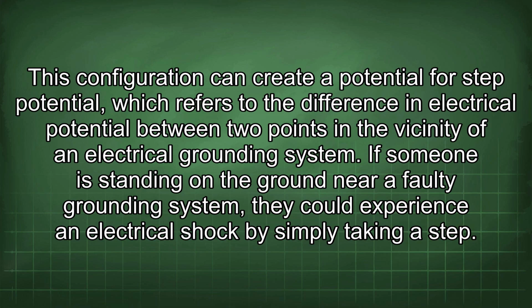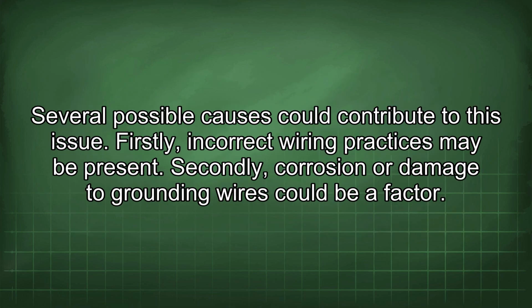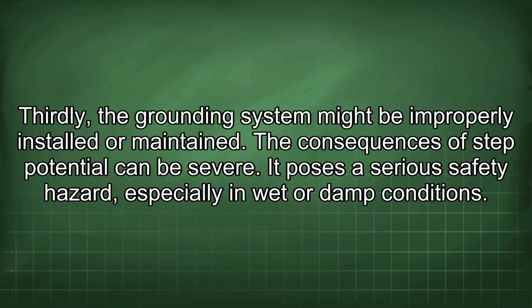If someone is standing on the ground near a faulty grounding system, they could experience an electrical shock by simply taking a step. Several possible causes could contribute to this issue. Firstly, incorrect wiring practices may be present. Secondly, corrosion or damage to grounding wires could be a factor. Thirdly, the grounding system might be improperly installed or maintained.